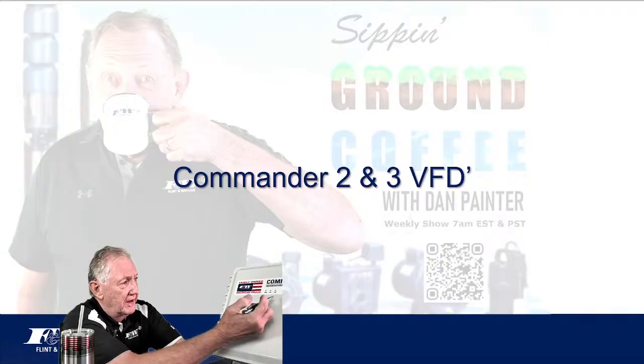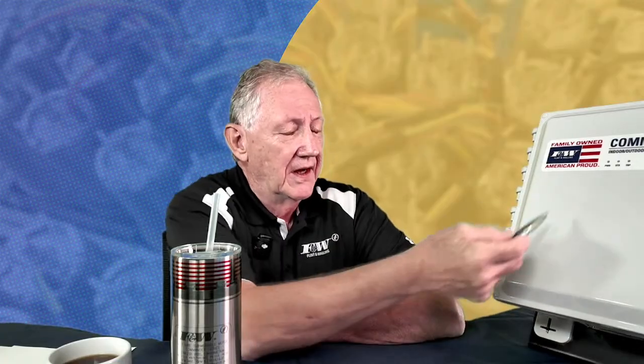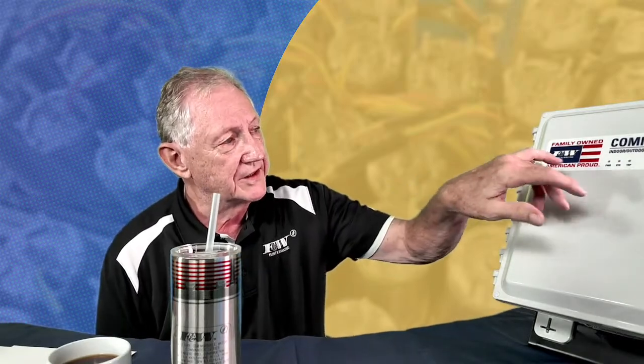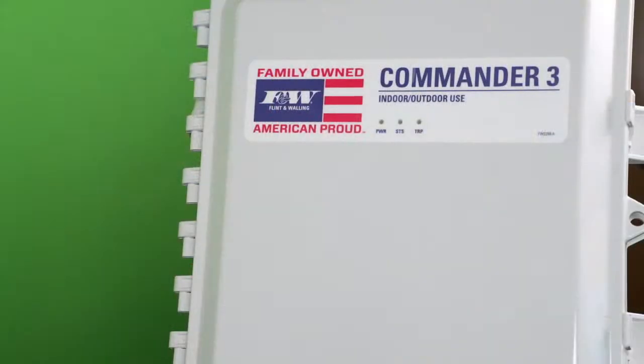If we look at the front of the drive, there's this 3-light interface. You've got a power, a status, and then a trip. Not buttons, but indicator lights. That power light, when it's on, will show a solid green, indicating that the controller is powered up. And the status light, depending on whether it's solid or blinking, is going to indicate the status of the drive itself. And then that trip light, whether it's solid or blinking, is going to indicate some kind of an issue with the system or the drive itself.